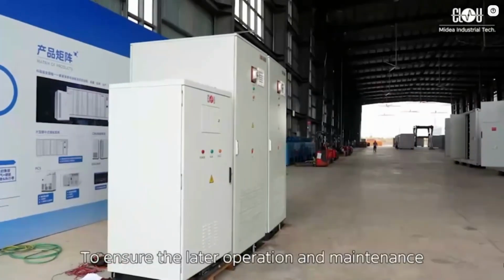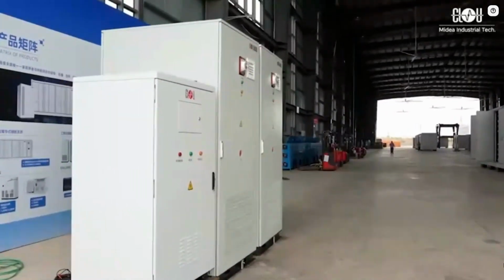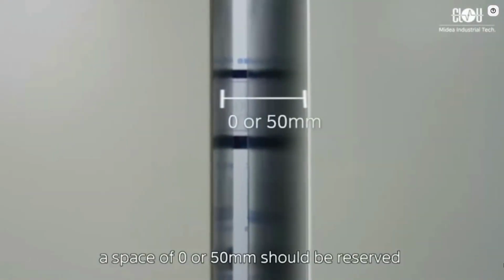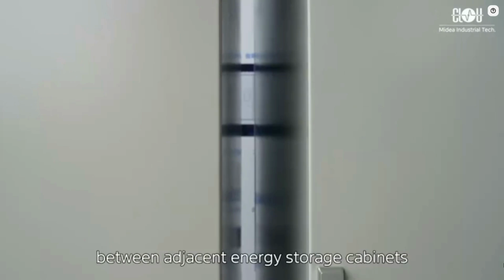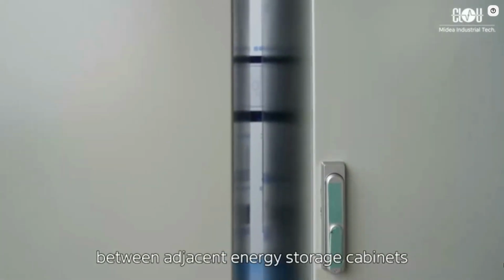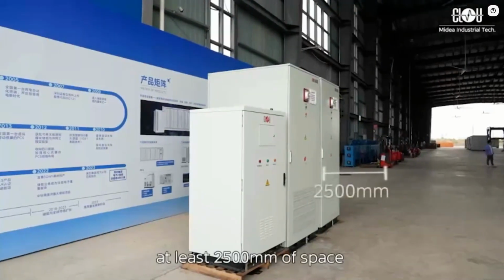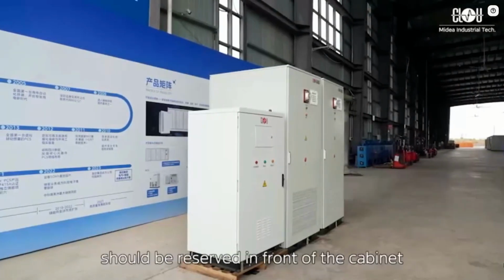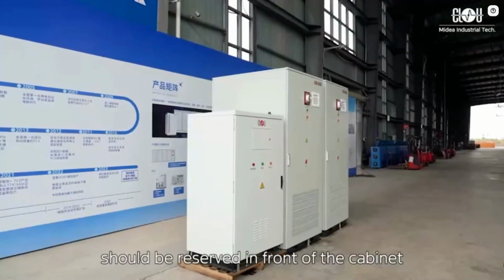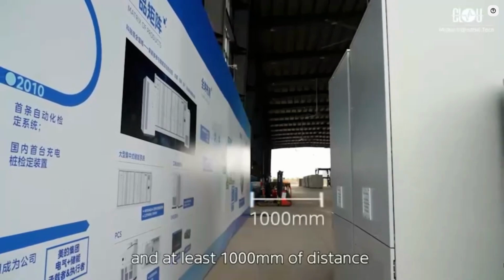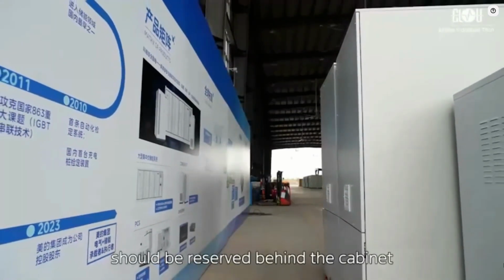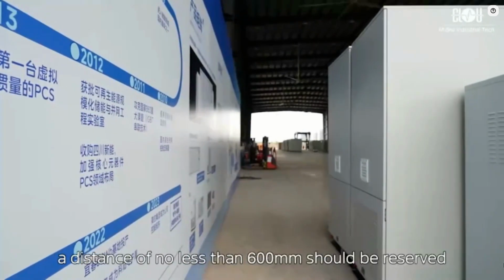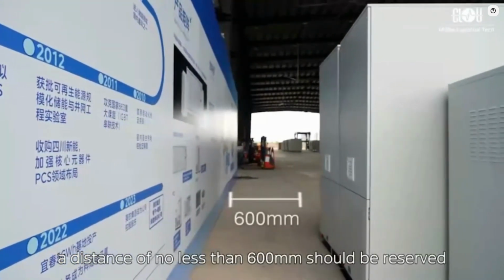To ensure later operation and maintenance, a space of 0 to 50 millimeters should be reserved between adjacent energy storage cabinets. At least 2,500 millimeters of space should be reserved in front of the cabinet, and at least 1,000 millimeters behind the cabinet. When space is limited, a distance of no less than 600 millimeters should be reserved.